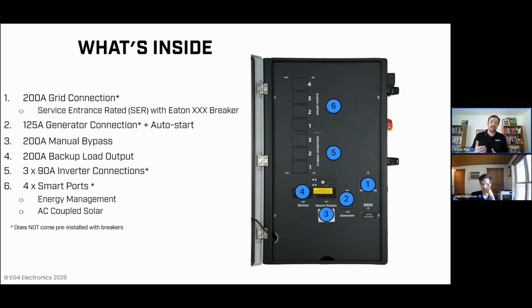Not only can that act as a means to actually manage loads on site, it'll also give the ability to attach non-traditional power sources like maybe an AC coupled solar system that exists already into the EG4 energy storage system and have that power source be controlled by the system, again, based on the considerations of the system, things like state of charge of the battery.